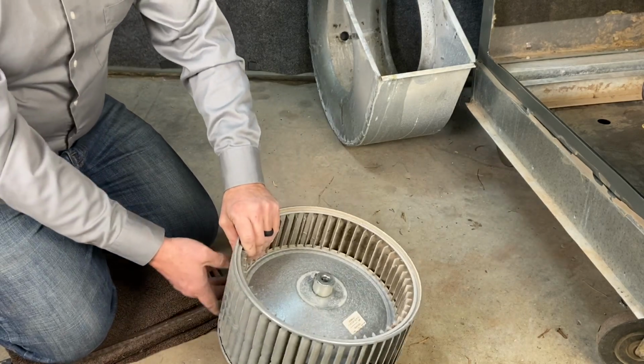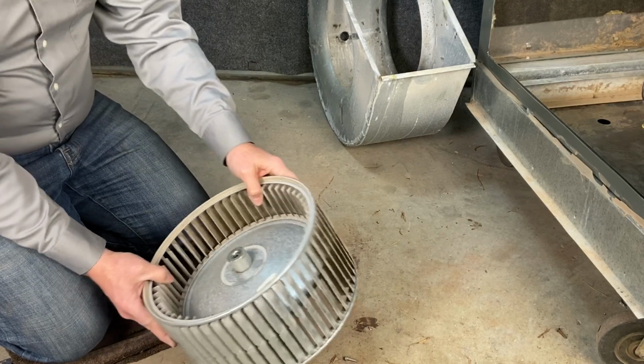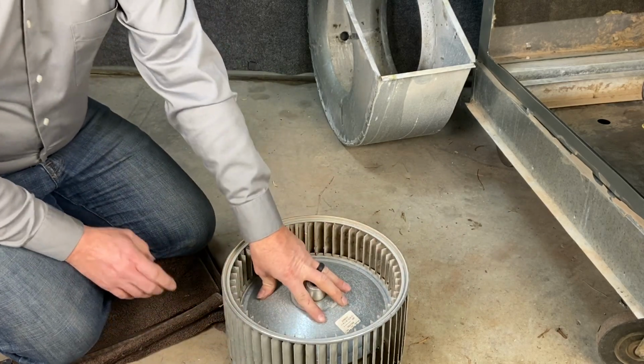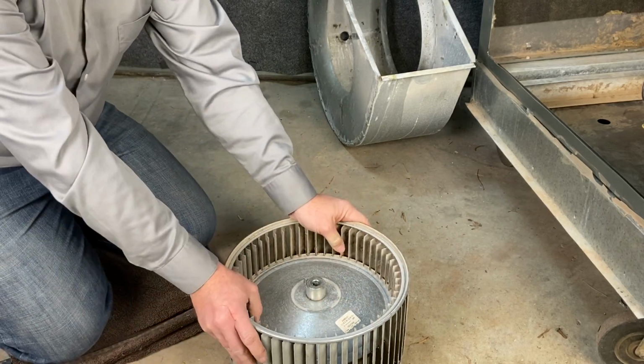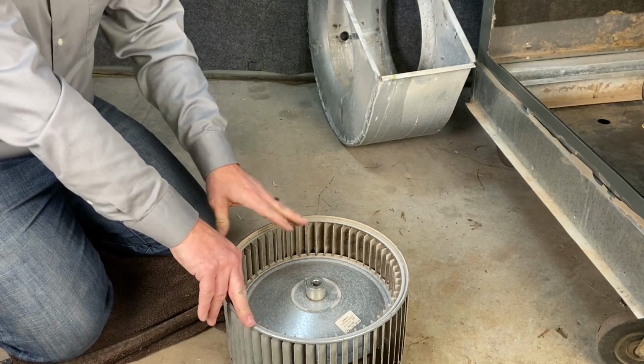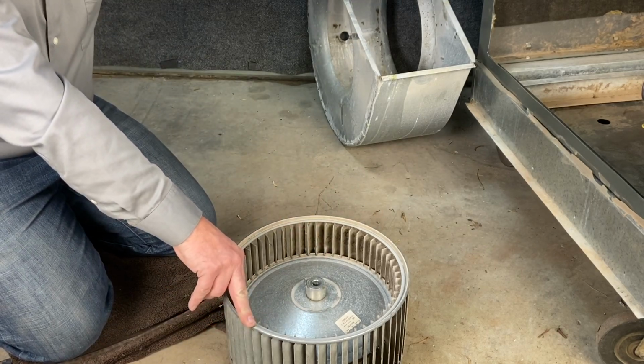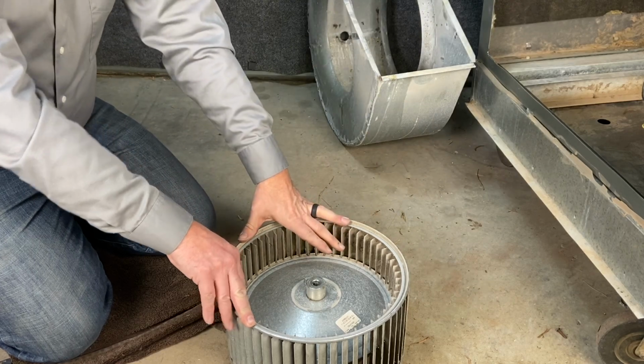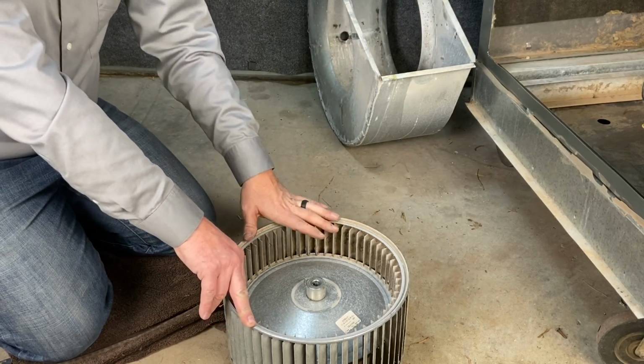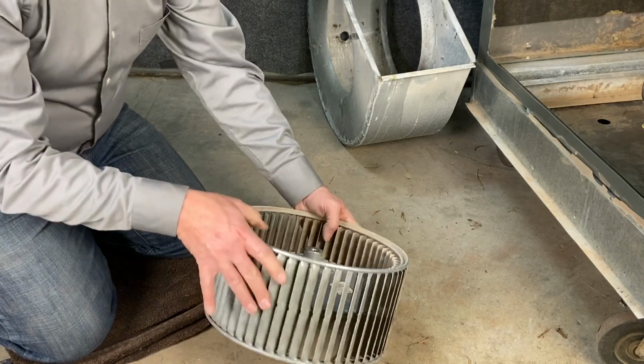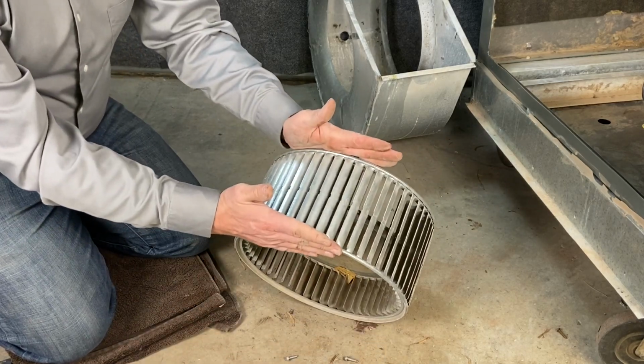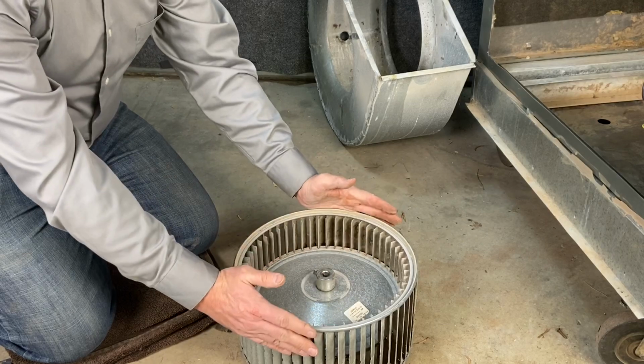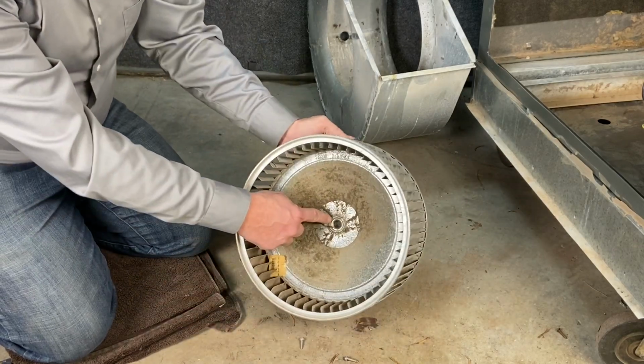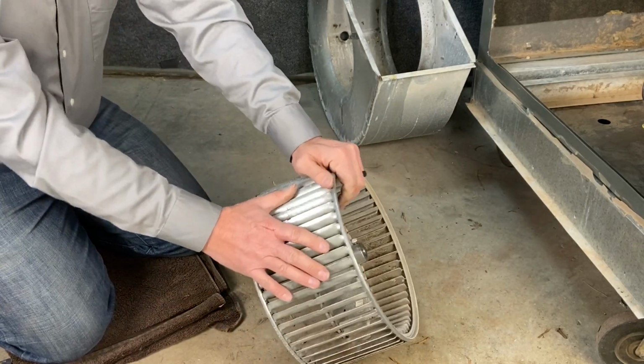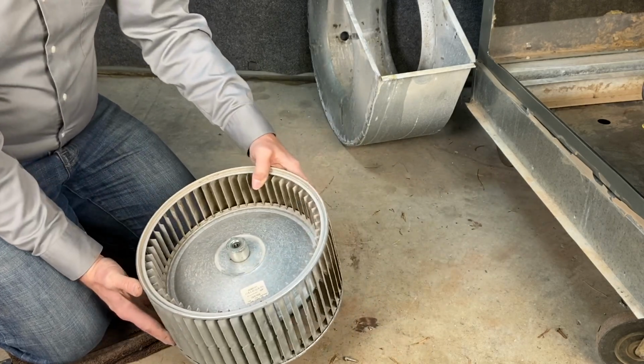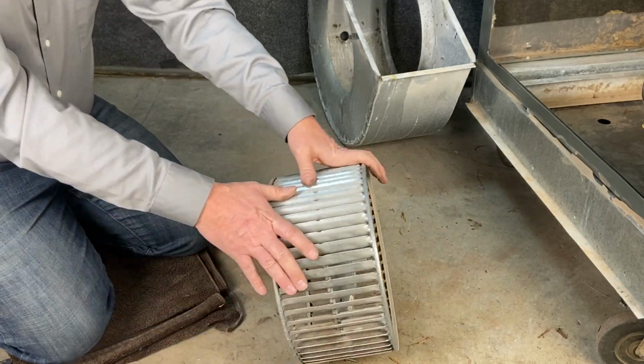If you need to replace this, this is going to be a part that you can take in with you. You can get the numbers off of it, but I found it's best just to take this wheel in and say, I need another one of these wheels. Ideally, I could go to the Rheem supply house and order a wheel with the model and serial number, getting exactly what I need, but you don't always have that luxury. So if you take this wheel in, you want to make sure you get it the correct width this way, the correct diameter this way, make sure you have the correct shaft size so that you can move it. And sometimes the new wheels will be heavier than the old wheel, so it'll affect the longevity of that motor.